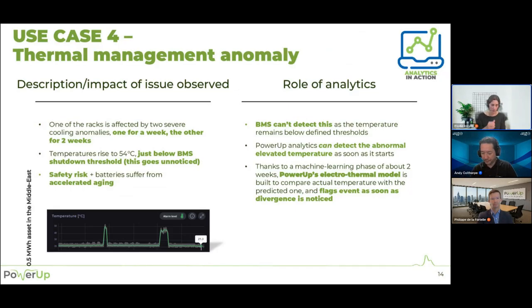So I'm going to show it to you right now. On this graph, you can see there were two peaks of temperature. But these two peaks weren't seen by the BMS because they weren't high enough to reach its threshold level. So the good point is there was no shutdown of the system. That's okay, but still the temperature went quite high, which is affecting the battery racks for days, maybe weeks, and the battery is suffering from it.